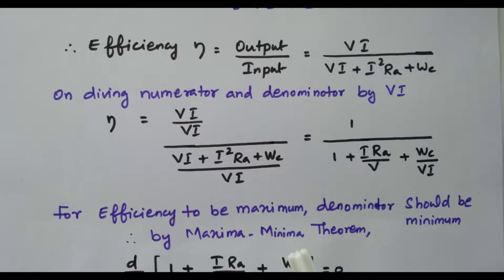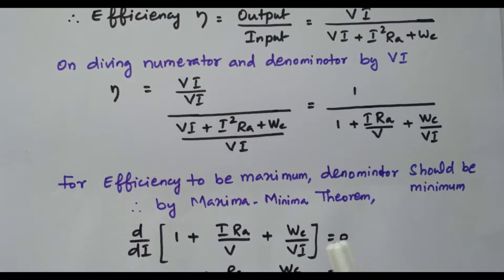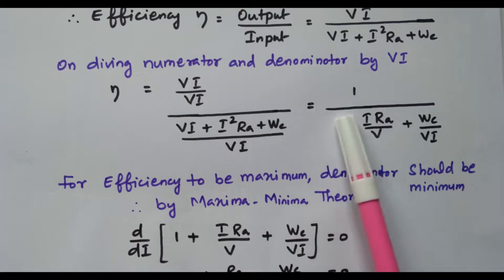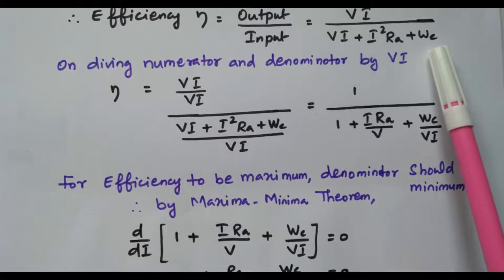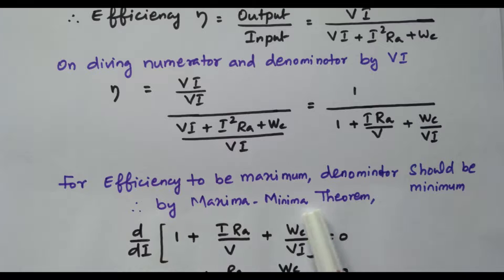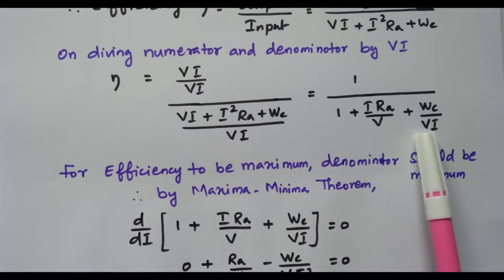For maximum efficiency, the denominator must be minimum. If the denominator — that is, the loss term — is minimum, we automatically get maximum efficiency. We apply the maxima-minima theorem: differentiate the denominator with respect to current I and equate to zero, because the losses are based on current.